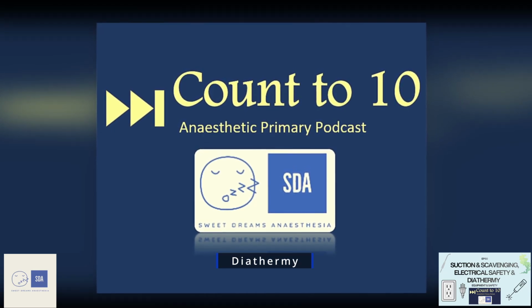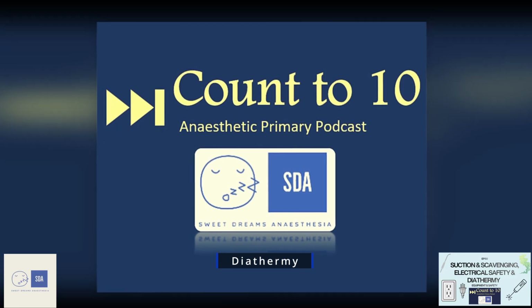Diathermy nowadays is very safe, but the first question you should be asking with regards to the main safety features is, why does diathermy, being a current that we're passing through the patient if it's unipolar, or if it's localized current in the form of bipolar, not affect the patient's heart? And this goes back to the currents that diathermy uses. Because of the very high frequency, these currents are too fast for the myocardium to then register and contract to. The myocardium's refractory period is too long to respond to the changes from the diathermy. Therefore, in most circumstances, it's very safe and is unlikely to cause VF.